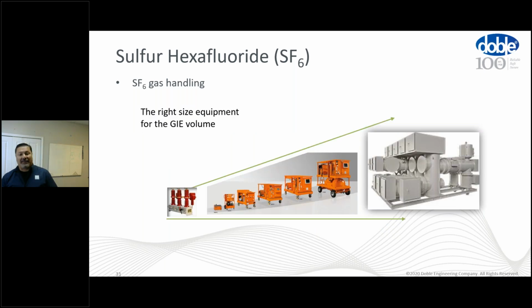So for example, having the right size equipment for the GIE volume. The smaller the breaker, not as large a recovery system or tools or equipment needed. The larger the GIE, the larger the recovery system. And I'll explain that further, but basically think about it this way. If you need to recover 100% of the gas, you're going to need a tool that can accomplish that efficiently, promptly, and safely.